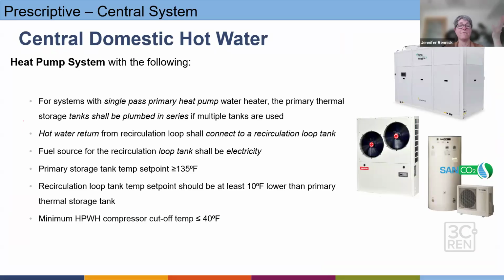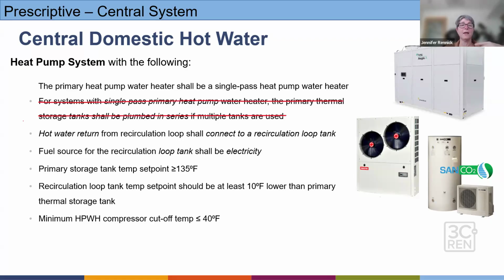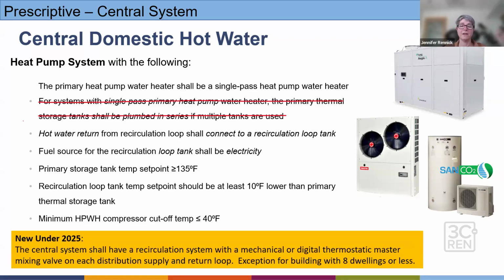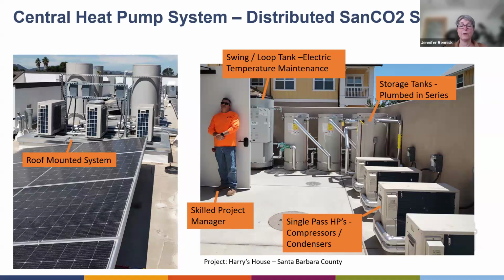And then, yes, you can have a central domestic hot water heating system that is the heat pump system. And then prescriptively, there's requirements for it. We used to have a requirement. Currently, it says if you have a single pass primary heat pump water heater, then the primary thermal storage tank shall be plumbed in series if multiple tanks are used. But that whole thing goes away. Now the new code just says the primary heat pump water heater shall be a single pass heat pump water heater. End of story, prescriptively. If you do something else, you can use the performance method. And then again, that electric or digital or mechanical thermostatic mixing valve. And this is just an example of what these split system, hydronic, heat pump central systems look like.